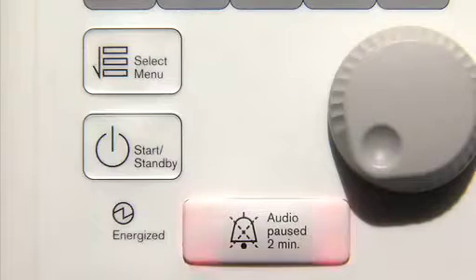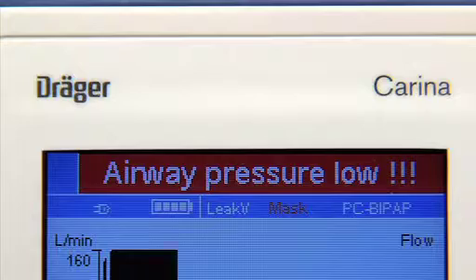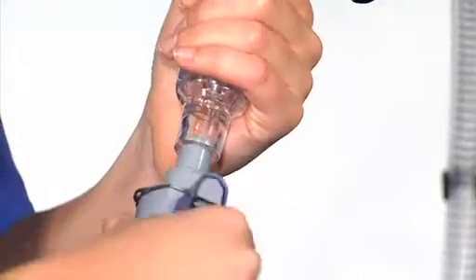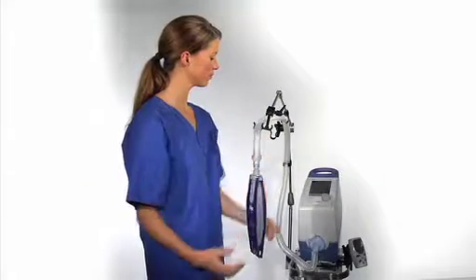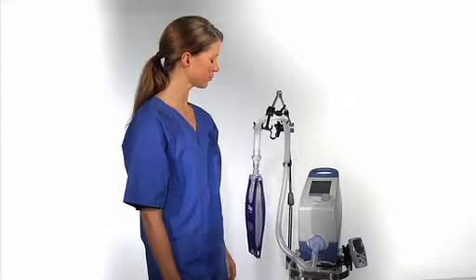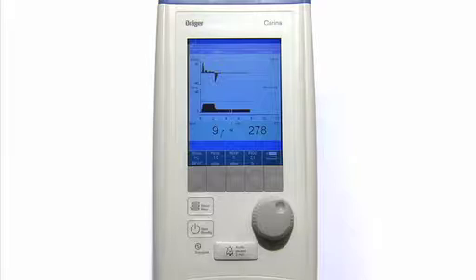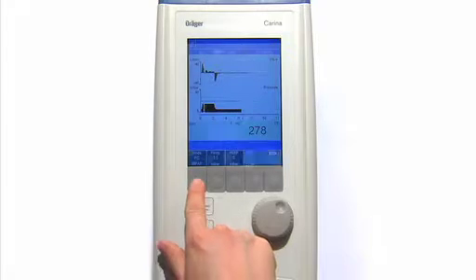Disconnect the test lung from the hose system. Immediately, an alarm tone will be activated and the alarm message "Airway pressure low" will appear. Please reconnect the test lung following the activation of the alarm. Please change ventilation settings to SPON CPAP.